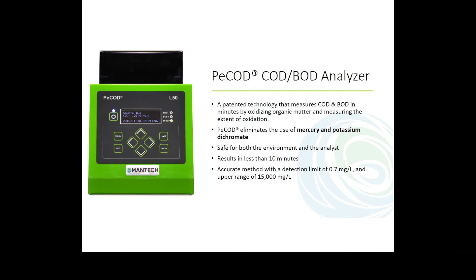It's based on nanotechnology, using TiO2 nanoparticles, with photoelectrochemistry as the core chemistry. The blue chip oxidizes and cleans up the wastewater or source water, like a lake or river, coming into the analyzer. The TiO2 forms hydroxyl radicals with high oxidation potential, cleaning it up, and it's connected to an electrode, the black piece below the blue PeCOD sensor.